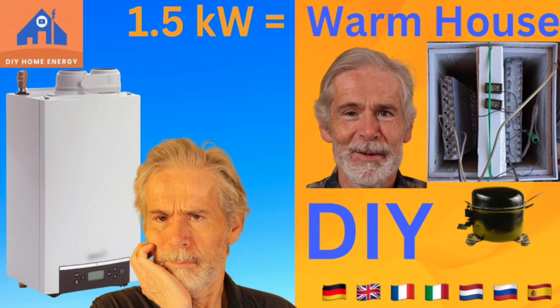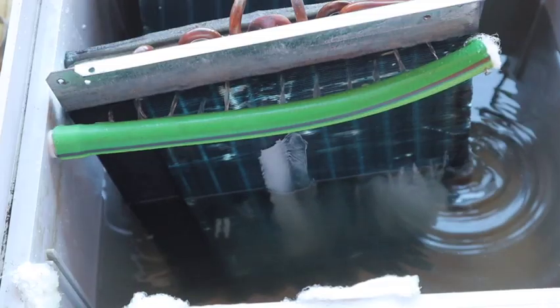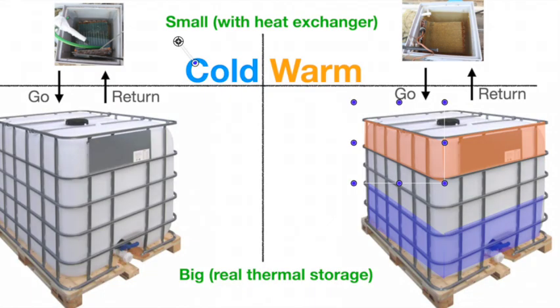Hello dear energy innovators. Here's the second part of the follow-up on video 71, where I showed how I realized the thermal energy storage with heat pump as an alternative to the natural gas boiler and made my hands dirty. I will now show the remaining topics. How I dealt with the central heating circuit of radiators and the new pump. I will revisit the water boxes, the way to avoid ice formation around the evaporator, and how to use the temperature stratification strategy to improve the efficiency of the heat pump.